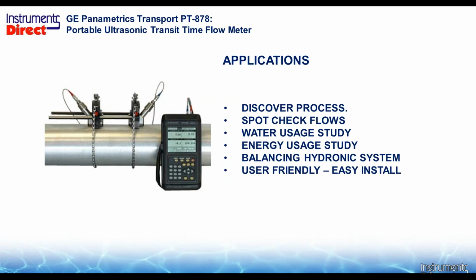What do we use a portable flow meter for? We use it for the discovery process. And that means: how much flow do I have inside my pipe? Do I need to buy a new chiller? Do I need to bill somebody for more use of water? I need to monitor my energy use. Portable, clamp-on technology is a very, very effective way to do a discovery process to justify additional investments.